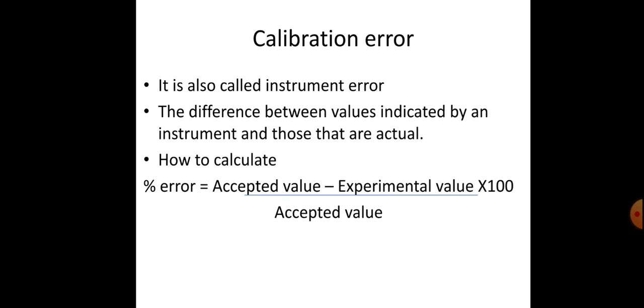Then how can we measure or calculate the calibration error? It is calculated as percentage error equals accepted value minus experimental value, divided by accepted value, multiplied by 100. Calibration error is an instrument error, the difference between values indicated by an instrument and those that are actual. So, as already told, percentage error equals accepted value minus experimental value, divided by accepted value, multiplied by 100.